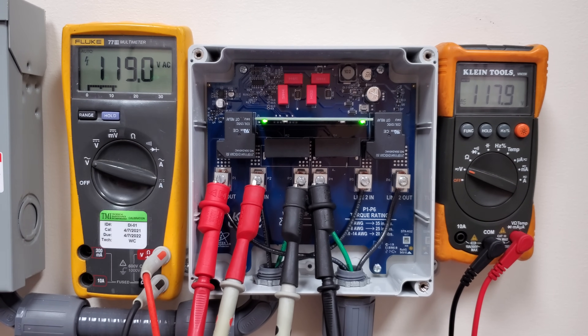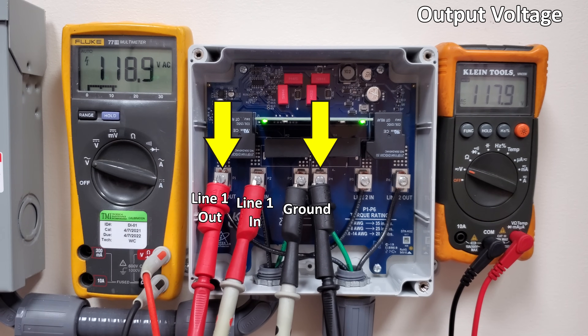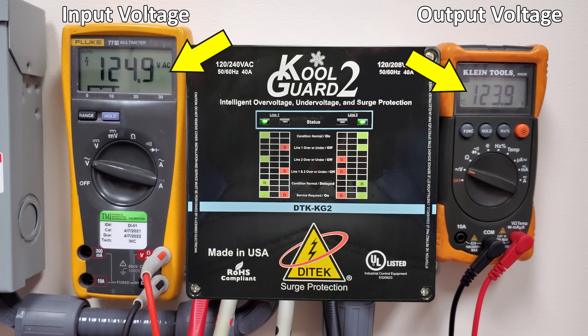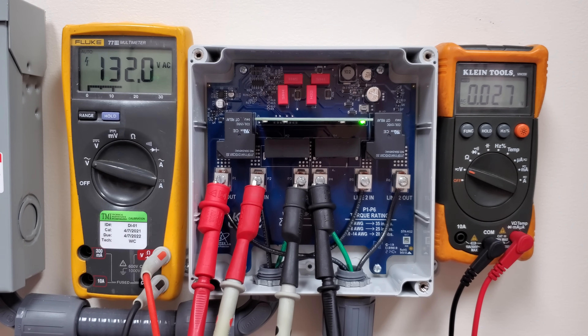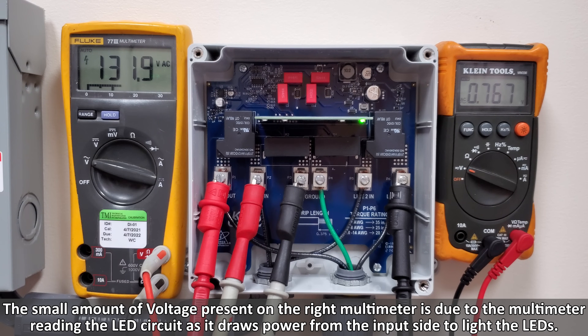We have one multimeter on the left measuring input voltage on one of the two legs, and the multimeter on the right measuring output voltage. Scenario one is over voltage. You can see the voltage rising up to about 130 volts before the KoolGuard 2 opens the electrical circuit — the right multimeter now reads zero volts. Moving the probe to measure hot to hot, we still see zero volts instead of 240. So even if just one leg is over or under voltage, it breaks the circuit for both hots.